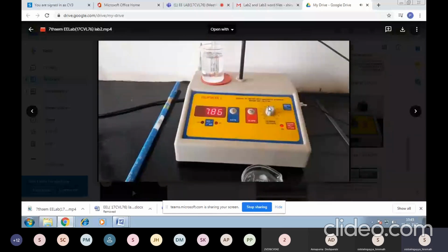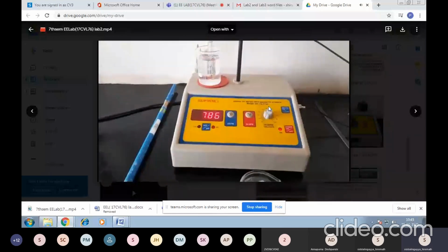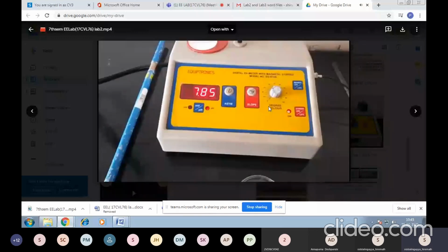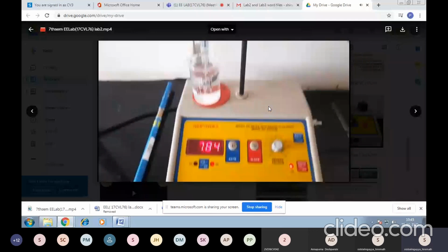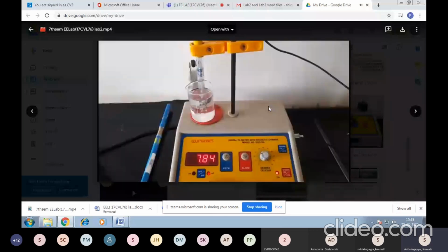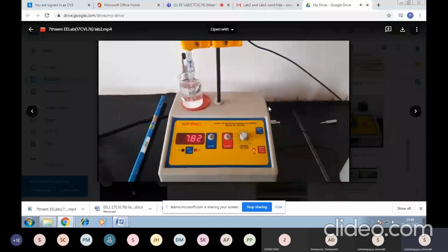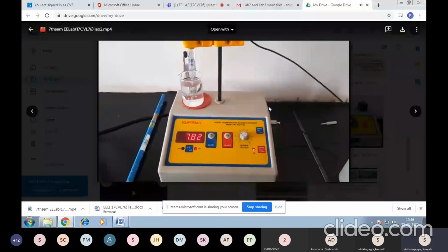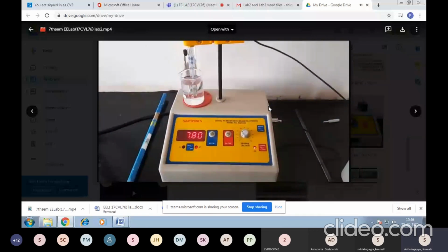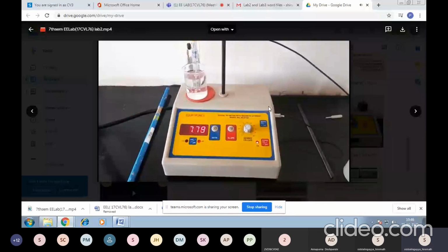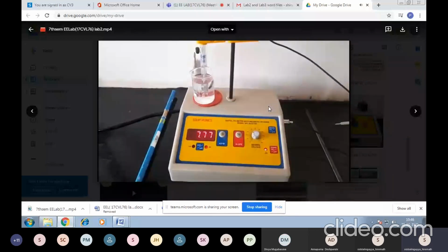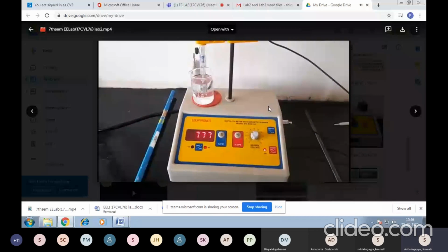performed by the instrument. In pH position, the pH reading of the solution in which the electrode is immersed appears on the display. In MV position, reading in mV, drop developed across the electrodes appears on the display. The polarity of millivolt drop also appears on the display in MV mode. Now, third step in calibration is combined electrode. BNC plug to be connected to BNC female marked electrode, that is on the side.